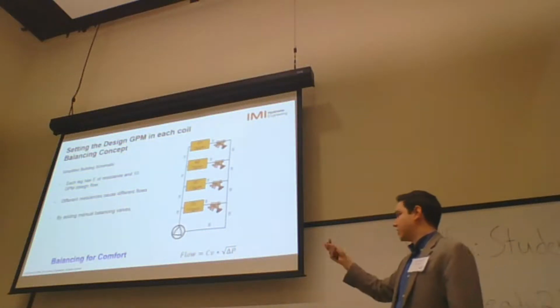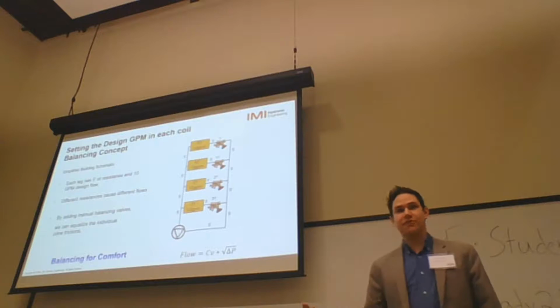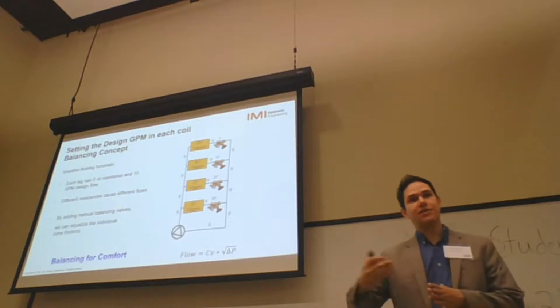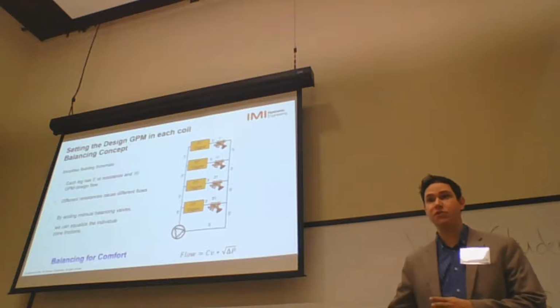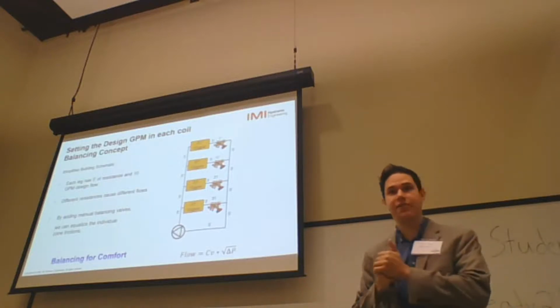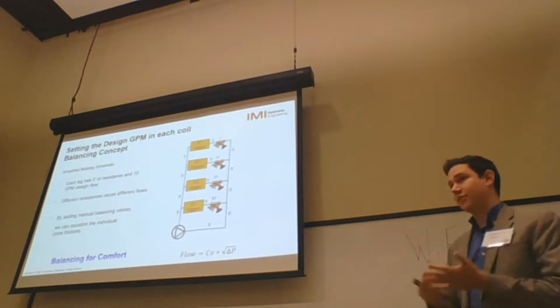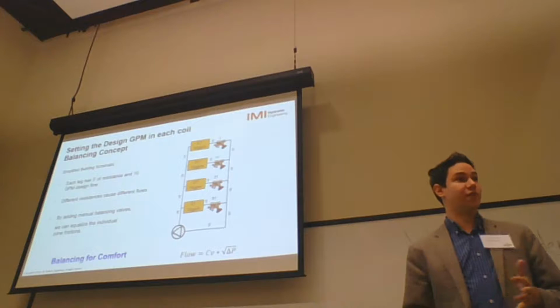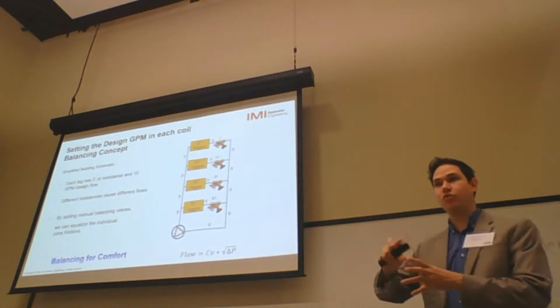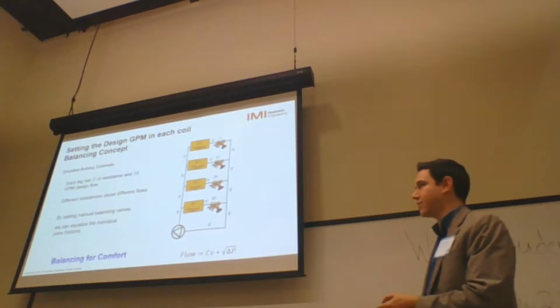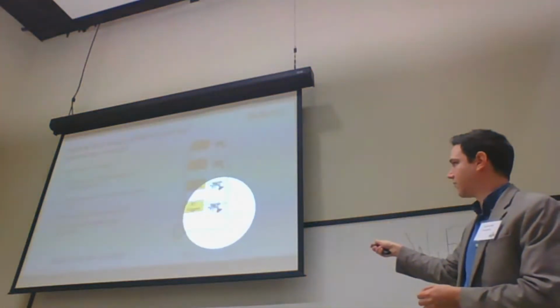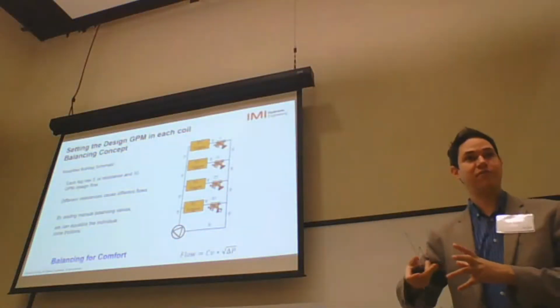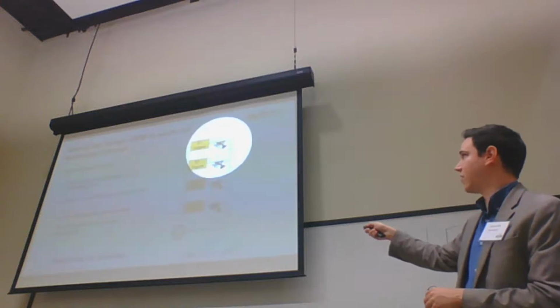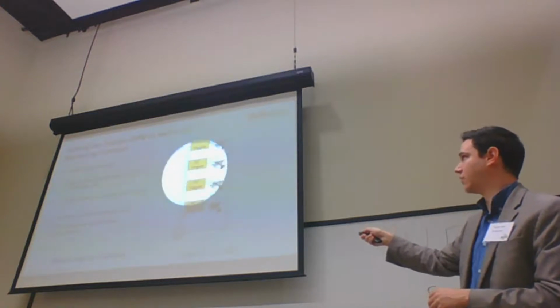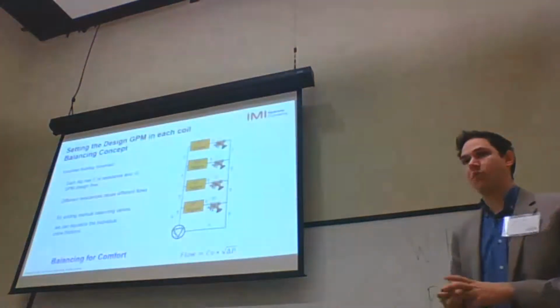This was basically the reason the first balancing valve was created: to equalize the pressure drops in the system. The first balancing valve was invented in 1957 in Sweden. And the idea was to replace the reverse return system with a device where I can control the pressure drop that I add to my installation. So when you look at this first balancing valve right here, I need to close it more, in this case at 31 feet, to get the total at 51. And at my index balancing valve, I'm getting 1 foot to also get the same 51. So all of them have equalized pressure drops.